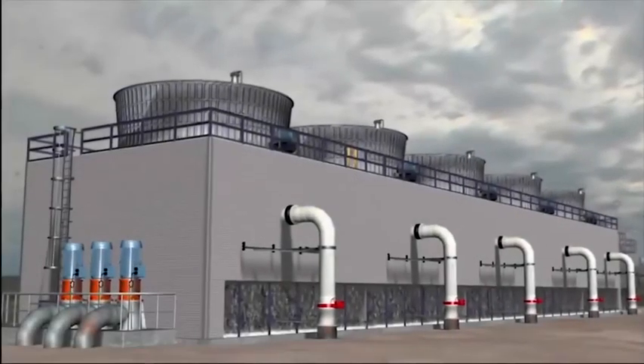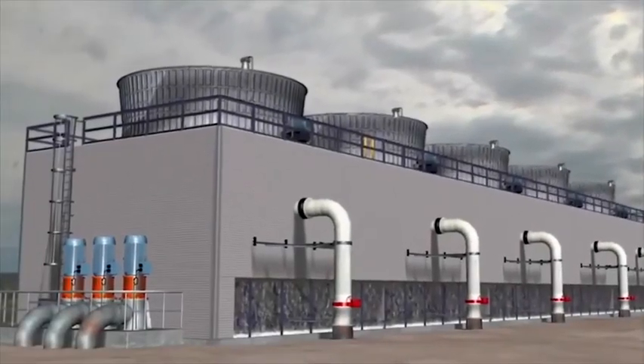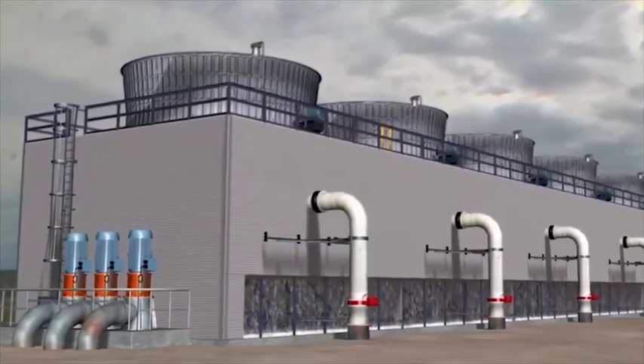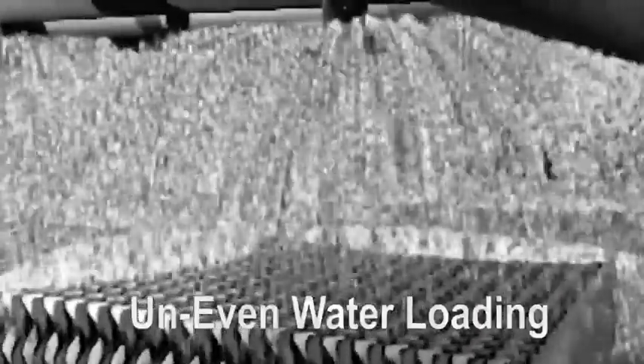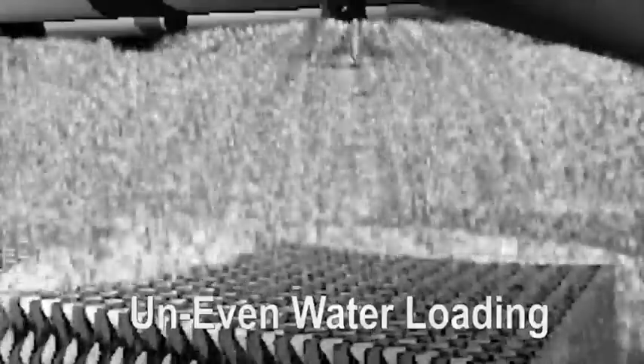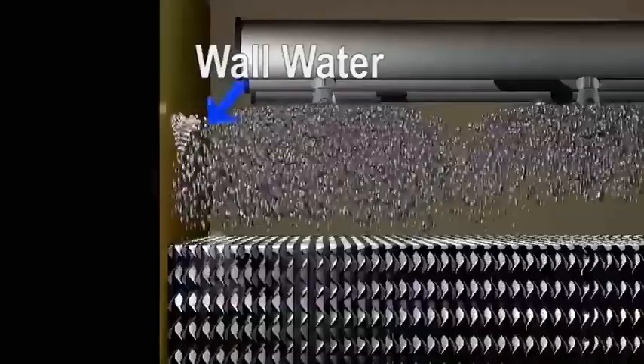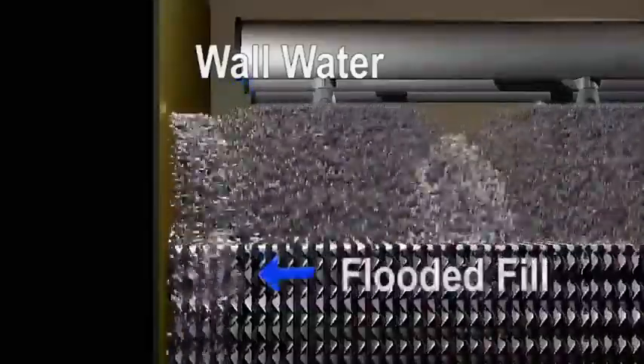Almost all of today's counterflow cooling towers have the same three problems that significantly downgrade their performance. Uneven water loading as a result of overlapping circular nozzles. Excessive wall water as a result of using circular nozzles, and inadequate water distribution systems.